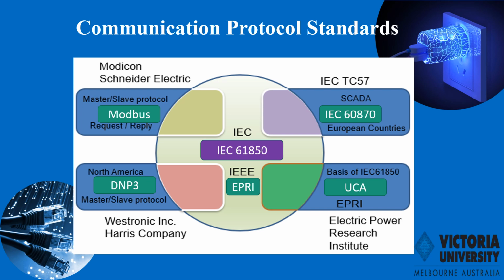The most common IED communication protocols that have found widespread use in the substation environment are Modbus, DNP3, IEC 60870, UCA, and IEC 61850. The Modbus protocol was initiated by Modicon. Basically, a Modbus at least must have a master device and a slave device to operate. The device requesting the information or signal is called the master, while the slave is the device supplying the information. The distributed network protocol was originally developed by Westronic. It is also a master-slave protocol platform, and it is popular in North America. The IEC 60870 standard was developed for protection and control of SCADA and associated telecommunications. It is famously used in European countries.